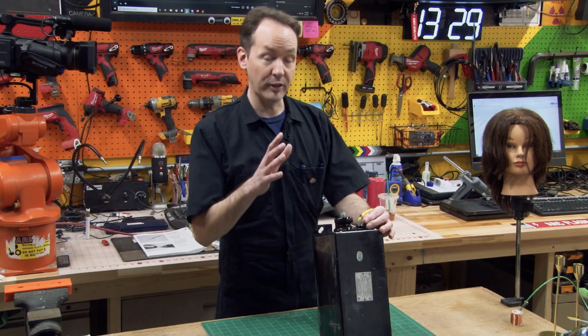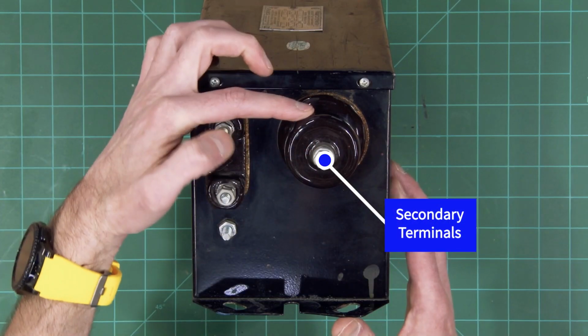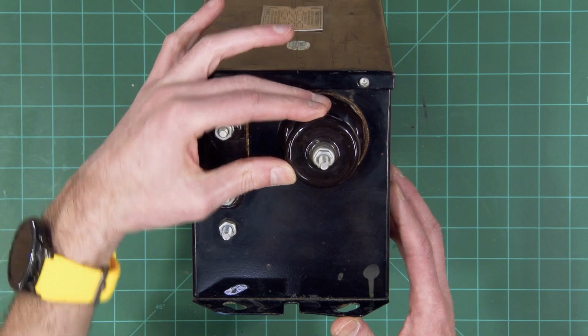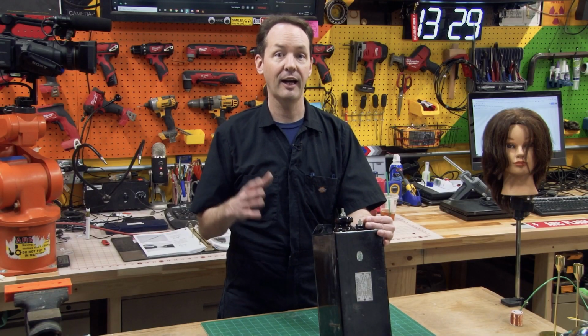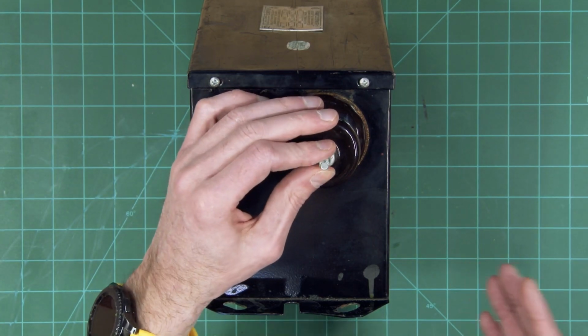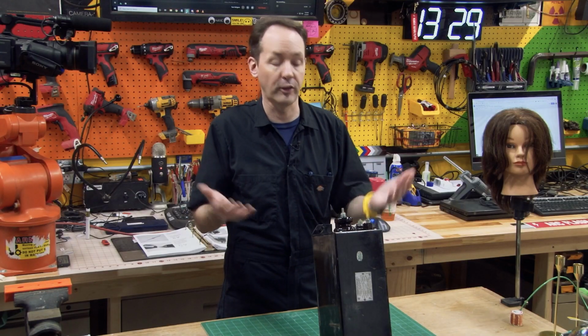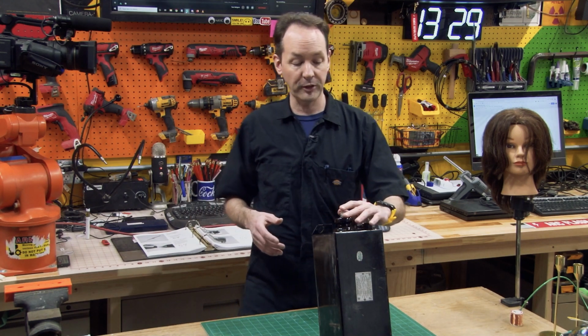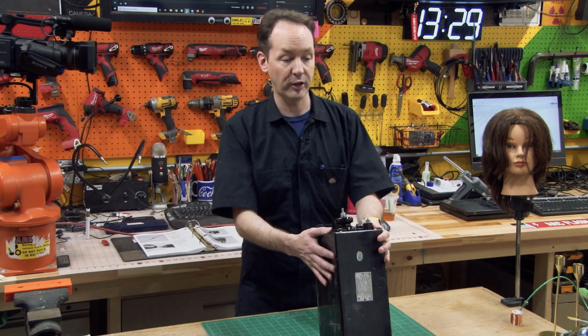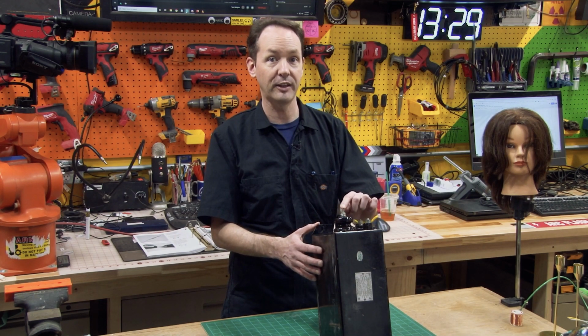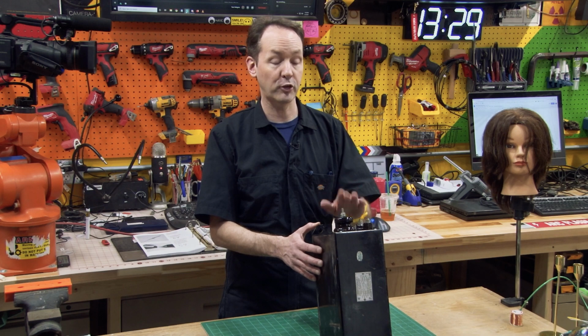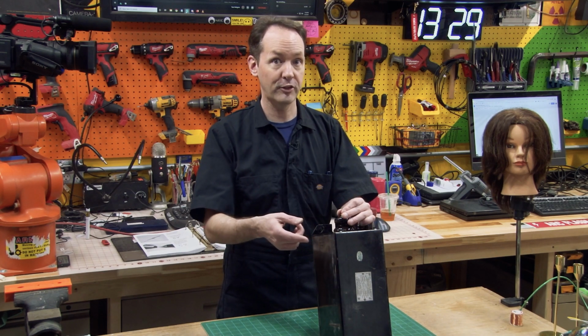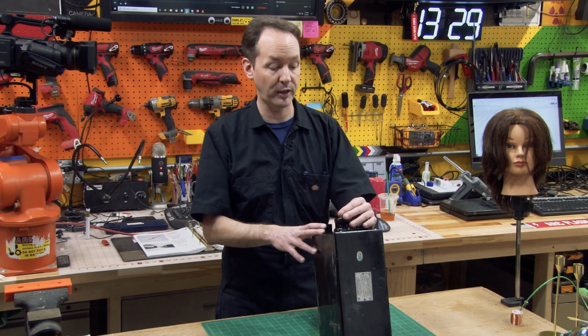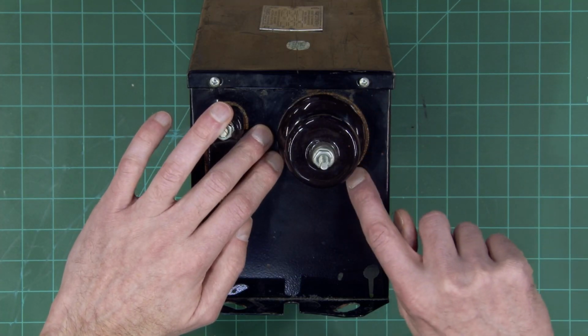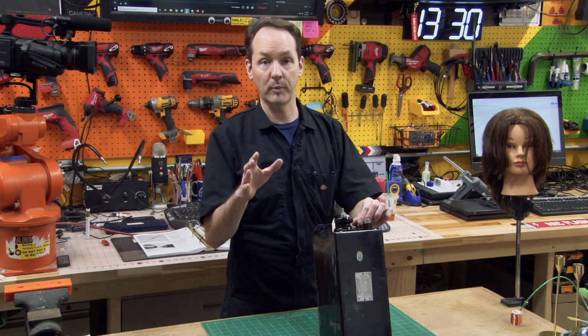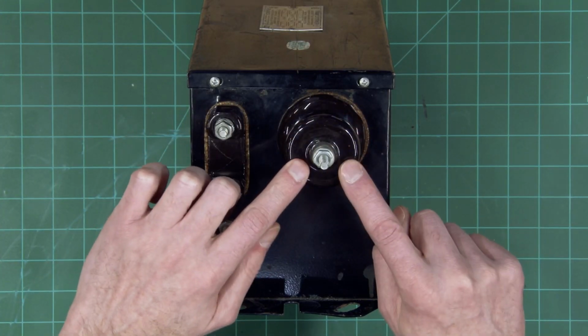The last terminal to know, and these are the big dogs, is your high voltage terminal here. The big ones with the big insulators are your high voltage secondary output terminals. These are the ones that if you touch, you die - that's really the important thing to know. On this particular transformer, this is a 12,000 volt neon sign transformer, so this is putting out 6,000 volts at any given moment relative to ground, and 12,000 volts relative to the other terminal. So it's serious business, you want to be careful with it. This also has the cork gasket down below - they don't all have cork gaskets, some have rubber - and the ceramic insulator up on top.